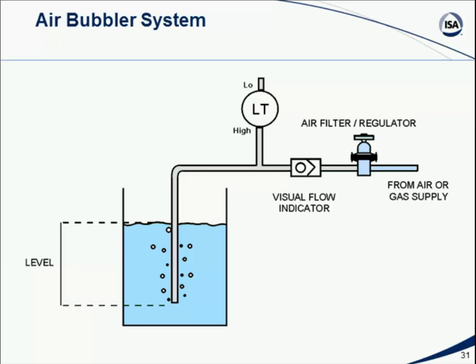In fact, bubbler systems are a very common way of measuring the level when we've got something that's really messy. For example, if you've got high viscosity fluids or something that's dirty or horrifying, where a typical measurement device would get gummed up, an air bubbler system just relies on pushing the fluid out of the pipe and keeping it out by a constant flow of air, so it's to a degree self-cleaning. Well, if we make a measurement of that back pressure, in other words, the amount of air pressure we have to push in to keep the fluid out of the pipe, that pressure is in fact proportional to the level of fluid in the tank.